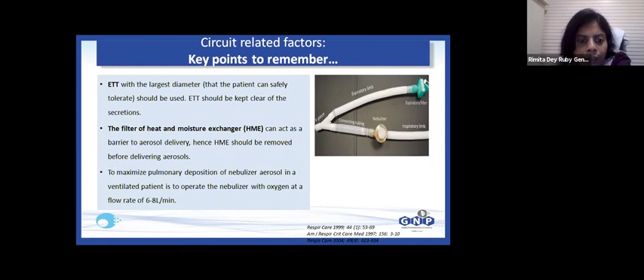And HME acts as a barrier to aerosol delivery. Hence, HME should be removed before delivering aerosols. That is a must point that has to be remembered. If you're placing the nebulizer in the inspiratory limb, but you have an HME in place beyond the Y, then your drug delivery is not proper at all. To maximize the pulmonary deposition of a nebulizer aerosol in a ventilated patient, you operate the nebulizer with an oxygen flow at the rate of around 6 to 8 liters per minute.